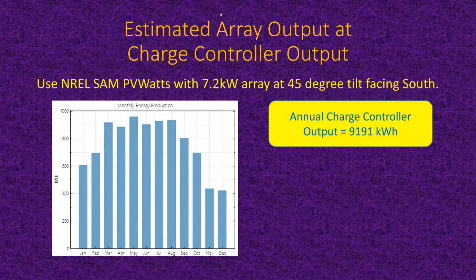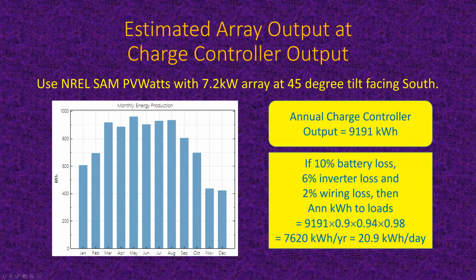So here's the deal. With this array, we can get 9,191 kilowatt hours out of the array. So what can we do with that 9,191? Well, now we have to work backwards and look at where the losses are. If we have 10% battery loss, 6% inverter loss, 2% wiring loss, then we can get 7,620 kilowatt hours per year, or 20.9 kilowatt hours per day on average to the loads. That's not hard to do, is there? These are nominal losses, the same losses we used last time: 10% in the battery, 6% in the inverter, 2% in the wiring, and all the rest of it can go to the loads. Okay, 20.9 kilowatt hours a day.